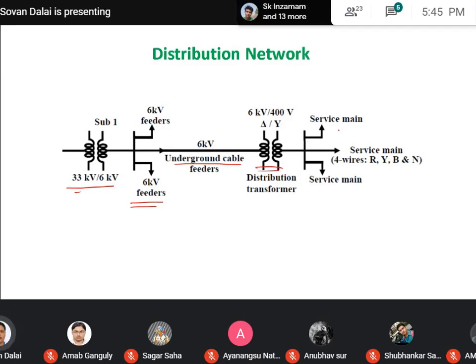And the distribution transformer's input is 6 kV and output is 400 volt. In your area, some of the transformers are situated in particular positions on the local road. That transformer is basically in the range of 415 volt by, let's say, 230 volt. 415 means the output is 400 volt, and mind that in West Bengal the distribution voltage level is 415 volt, so you better remember it as 415 volt. If you measure the voltage between the lines, that voltage level is basically 415 volt.